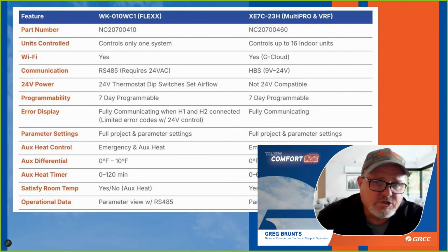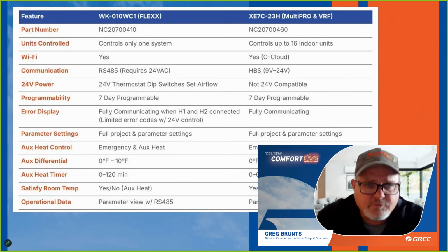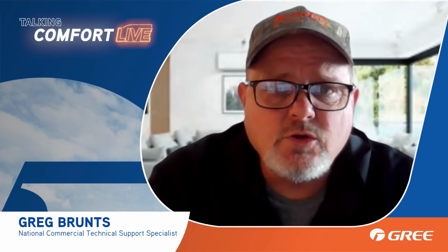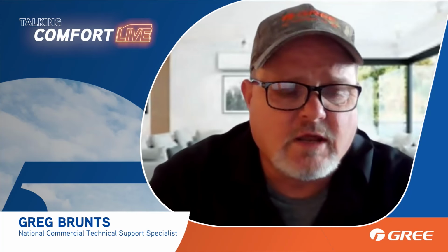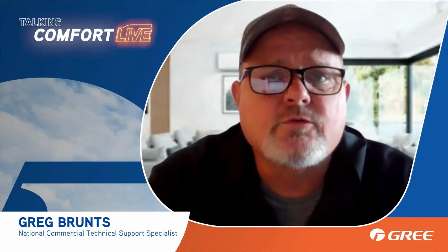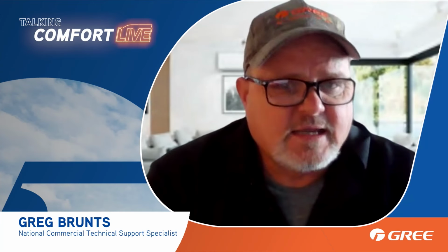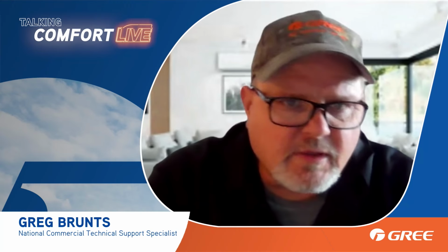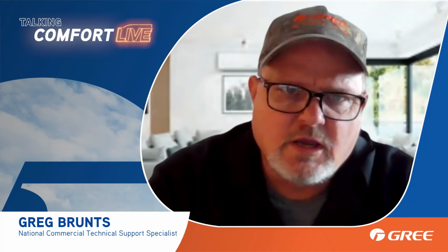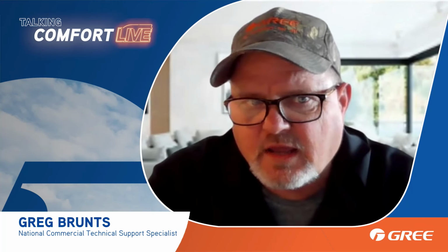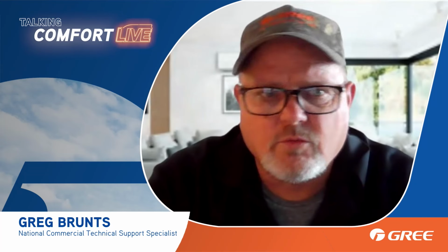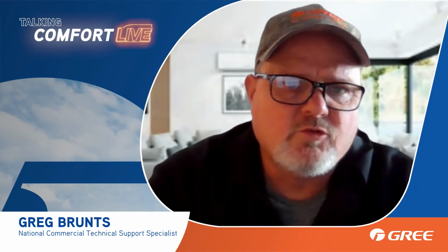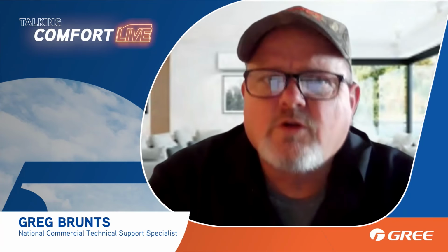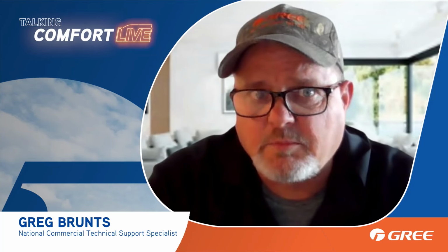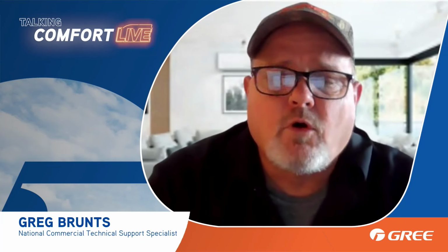Gotcha. The other thing, I was talking to JD about this just the other day. I think it's best for you guys when you're out there doing a FLEXX system, your H1, H2 now has to make the whole system communicate. So you have to have H1, H2 from the outdoor unit to the indoor unit, and also from there to the controller, in a daisy chain pattern. If you don't hook up the H1 and H2, it's not fully communicating. That's also why I have the 24 volt there: that thermostat is capable of being a regular 24 volt thermostat, or a fully communicating thermostat, depending on how you'd like to utilize that controller on the FLEXX system.